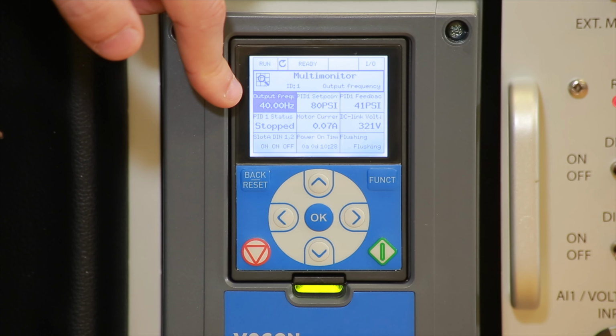We're going to use an induction motor, so we're going to skip through that. OK. The voltage, please look at the motor nameplate. Most of the information will be on there. So in our case, we have a 230 volt motor. We're going to change from 50 to 60 hertz by going left once and then up once. This changes it to 60 hertz.